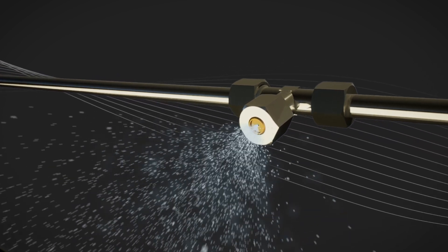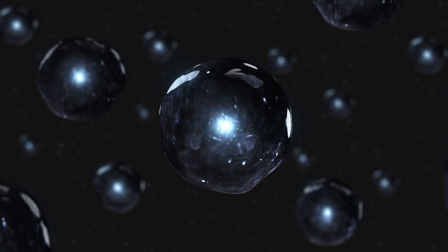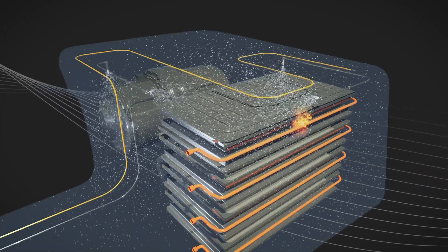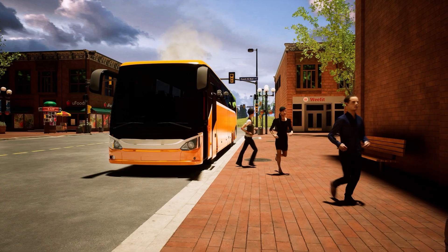The pressurized suppressant flows through the delivery system, ejecting the protective caps from the nozzles and dispensing a fog of atomized droplets to reduce any fire around the failed cell or other compromised system.